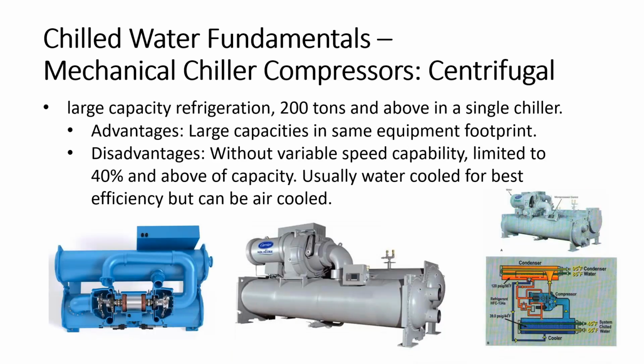So now we get to the big boy. The big boy is the centrifugal. One of the differences here is that it works basically like a water pump, except it pumps refrigerant gas. It uses a large impeller that rotates at a high speed. The one that has the cutaway on the left is actually a two-stage. If you follow the piping, it takes in refrigerant gas on the left, compresses it out the top, and then pumps that into the intake on the right, which pumps it into the condenser. So it uses one motor to drive two impellers at a high speed to boost up the gas to condense it. But these are designed to move massive amounts of refrigerant.